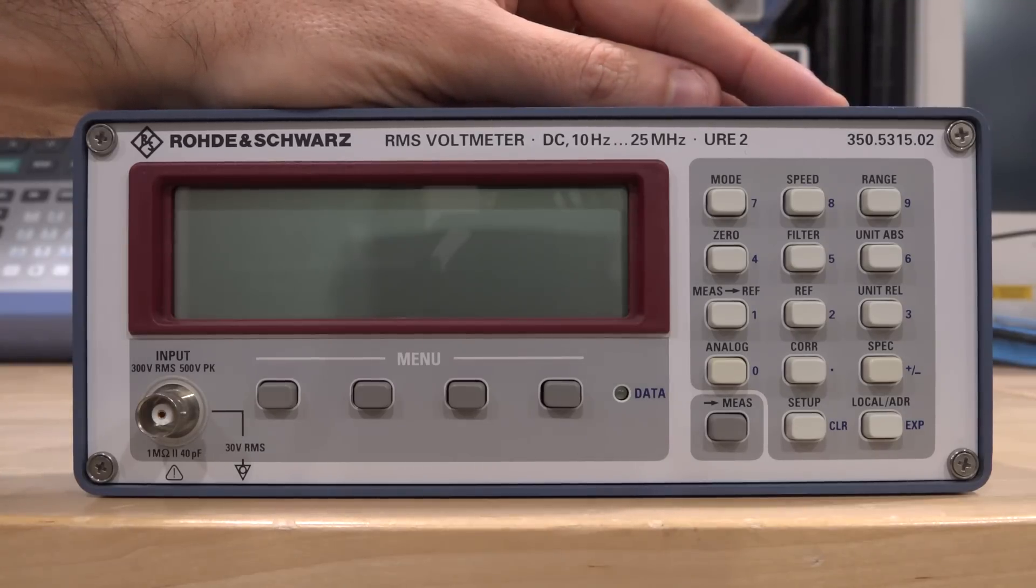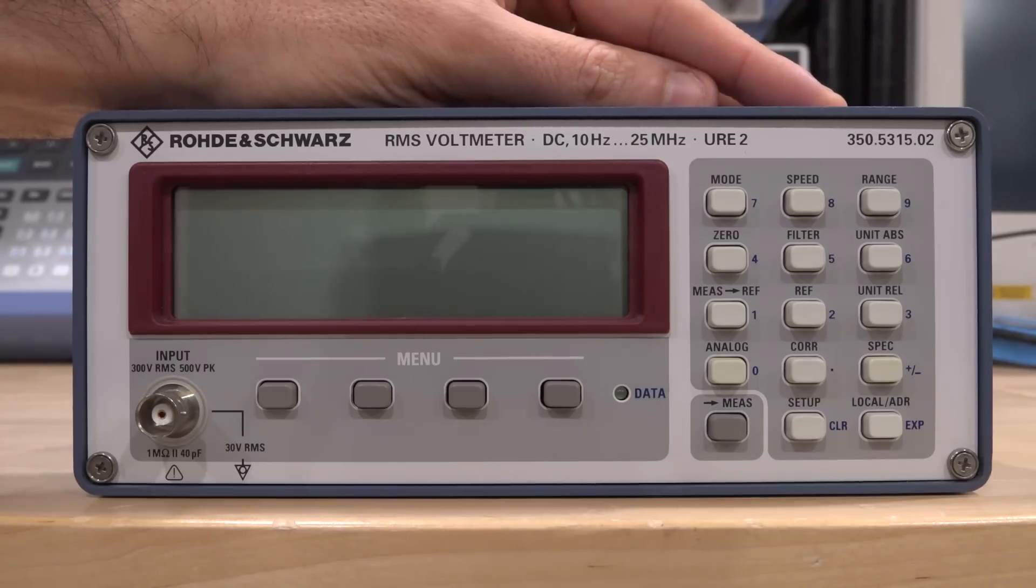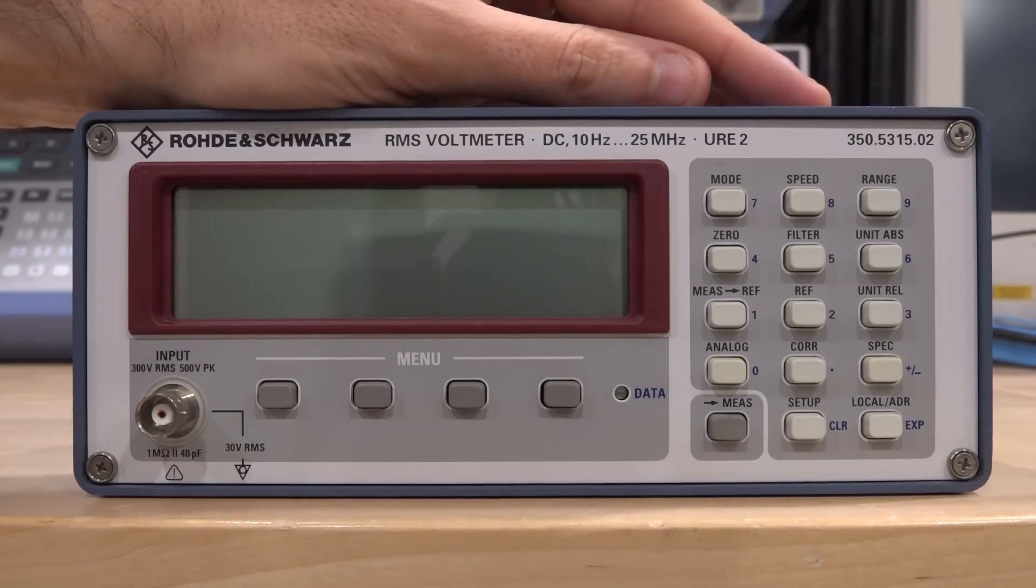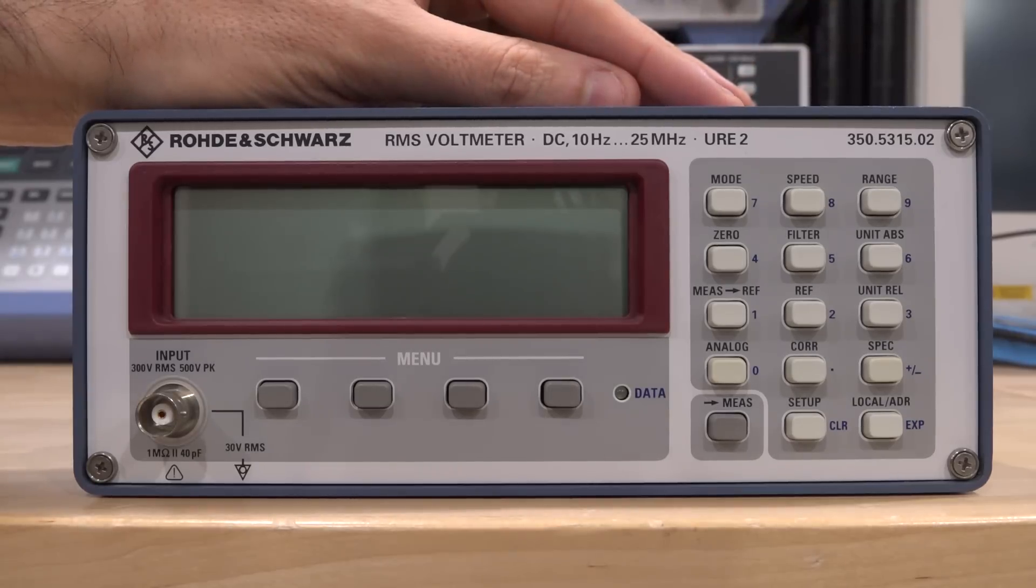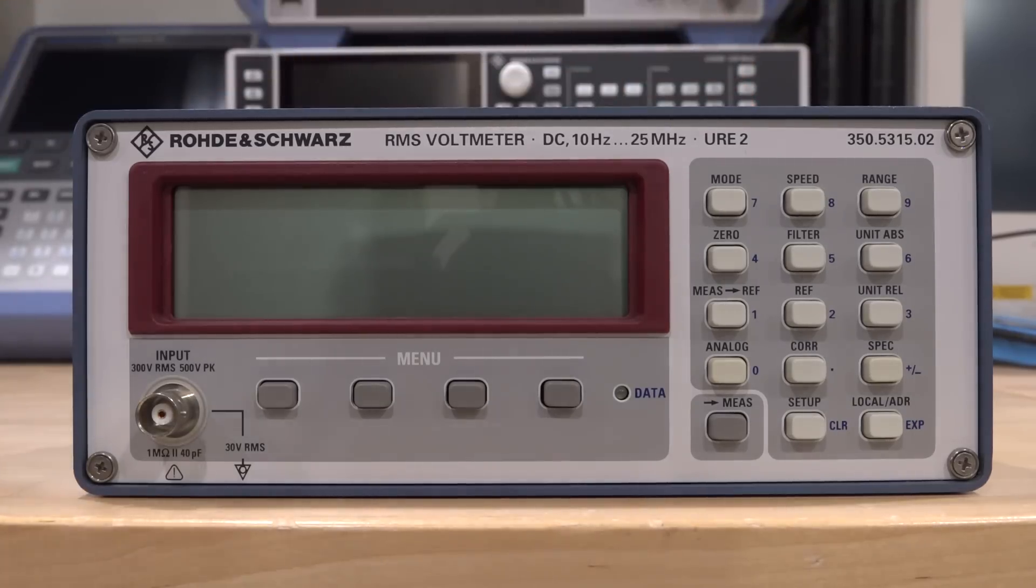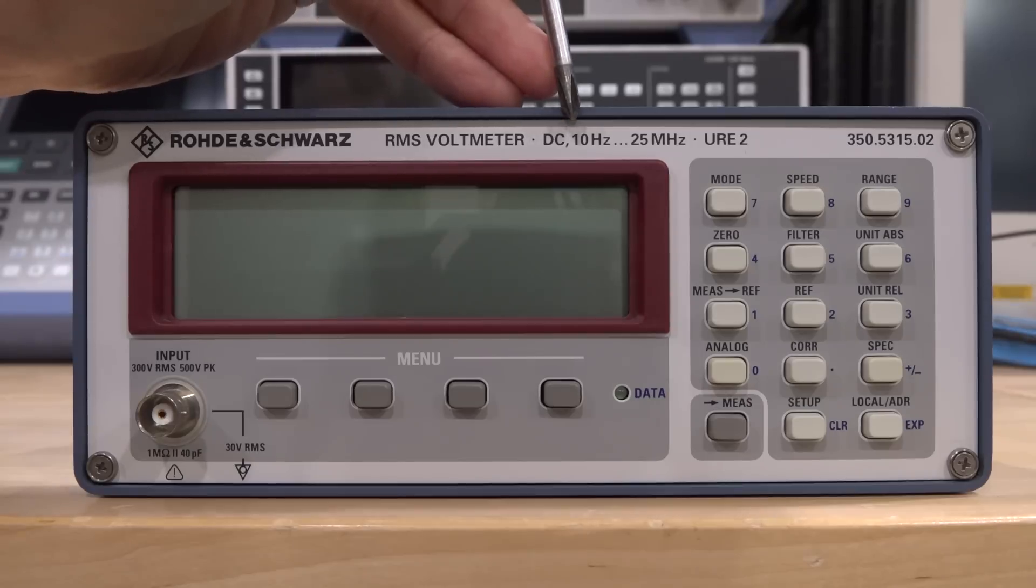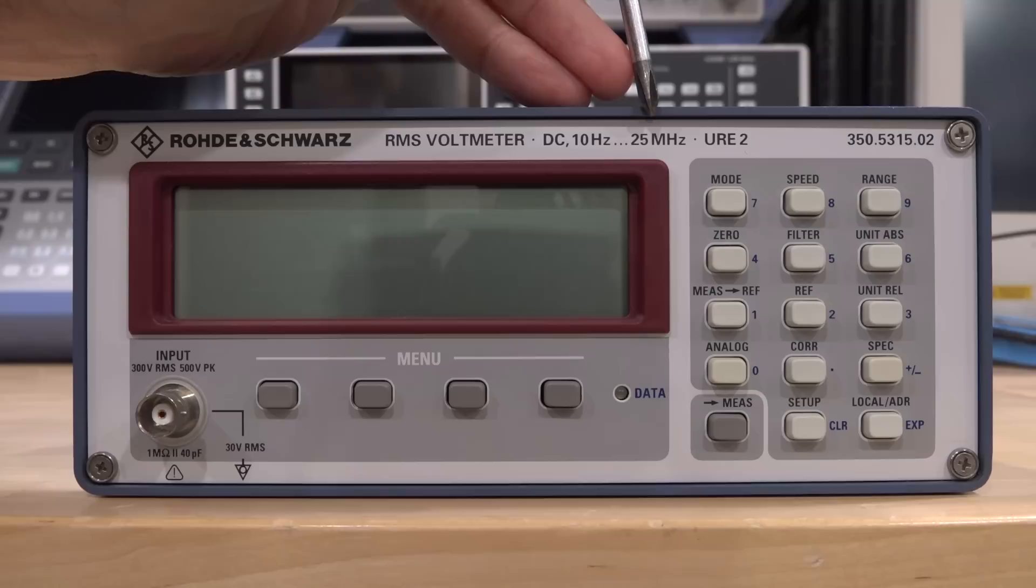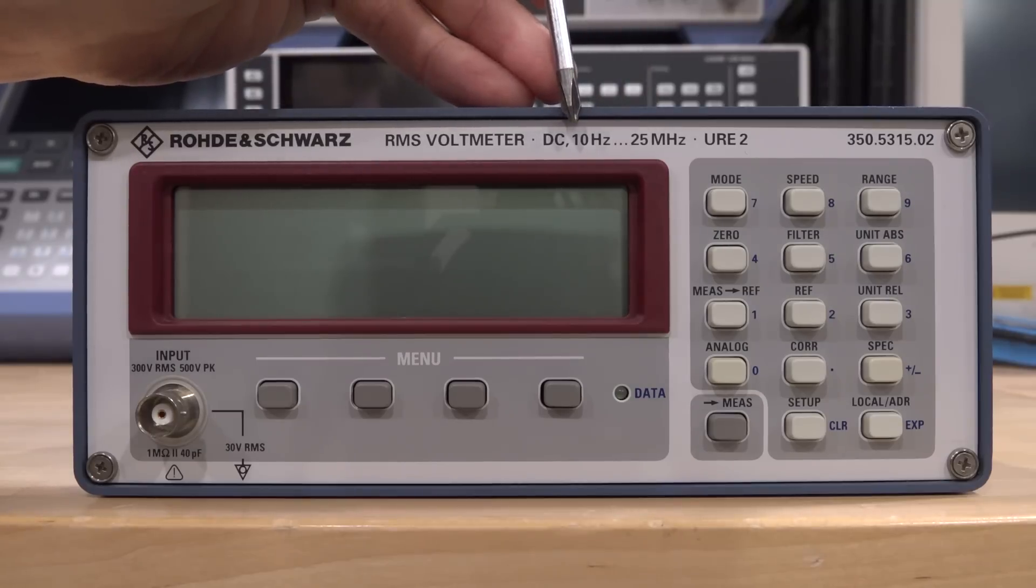It can measure very large RMS values and very large DC values simultaneously and give you precise RMS measurement. It's actually quite sophisticated internally. If you look at it, you'll notice right away there is DC, and then a comma, and then 10 hertz to 25 megahertz. This discontinuity already tells us something.